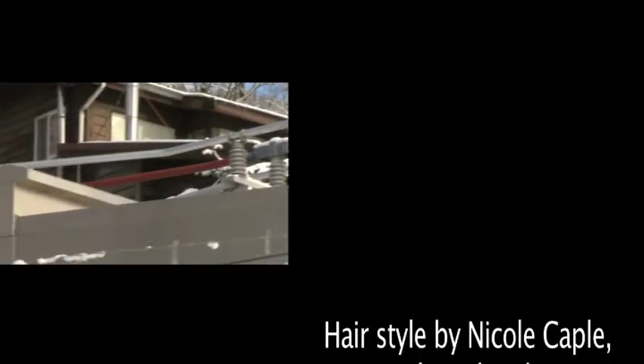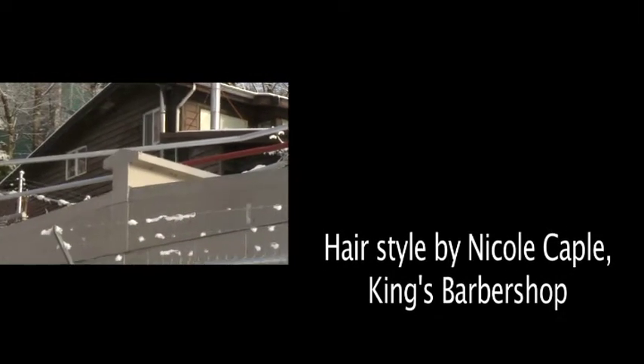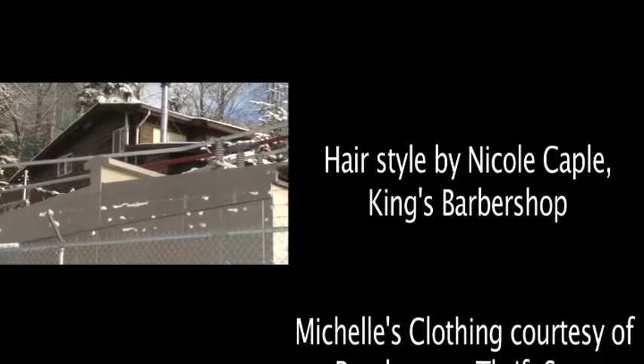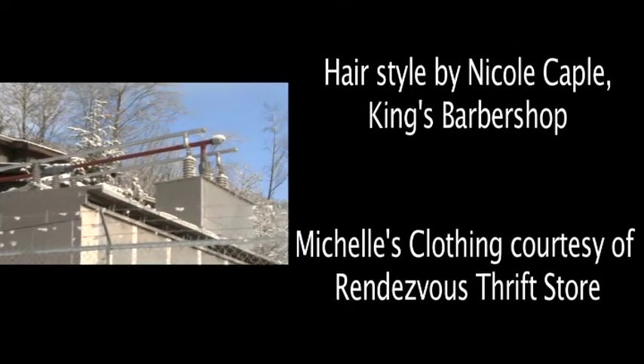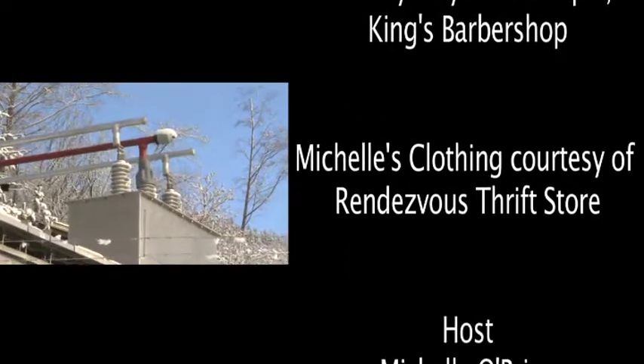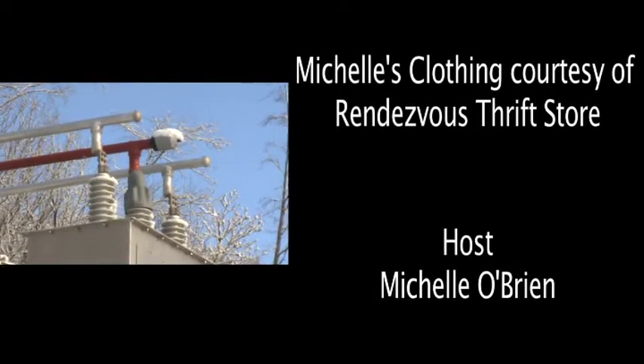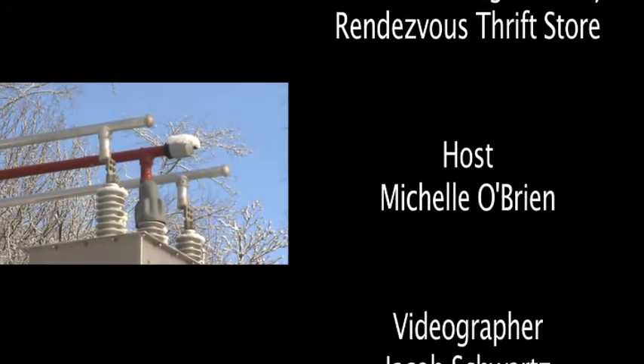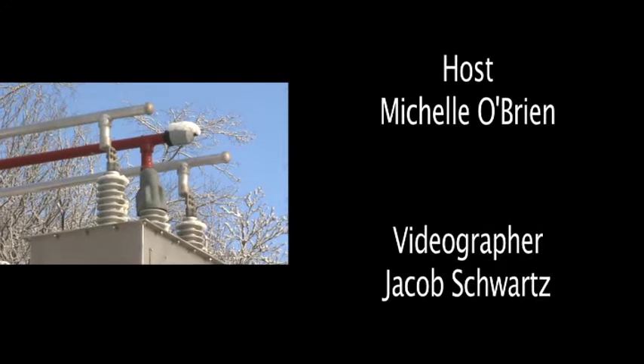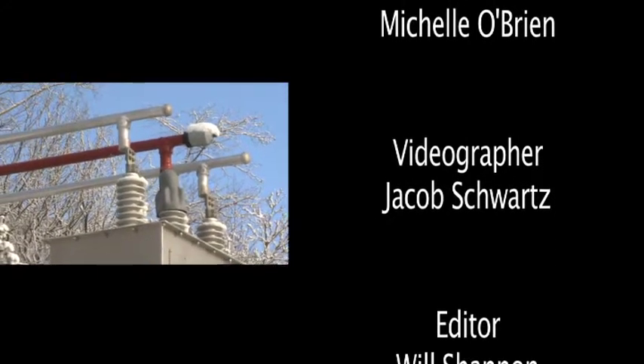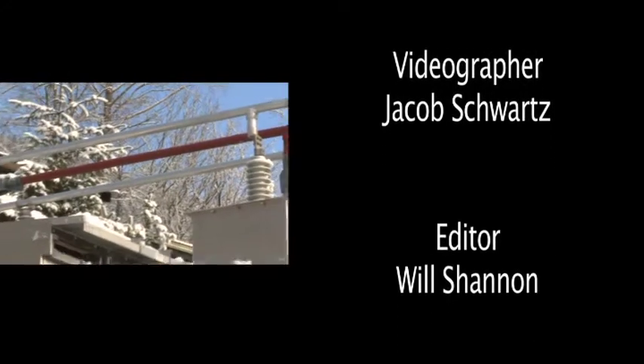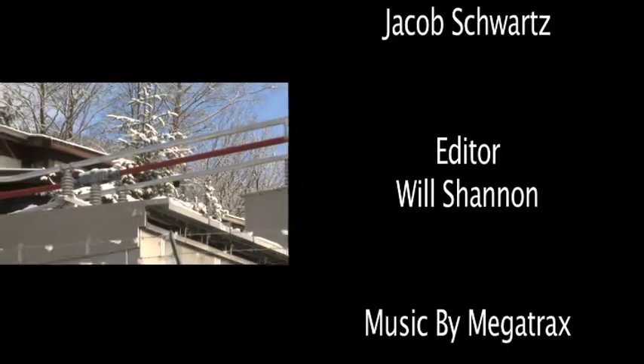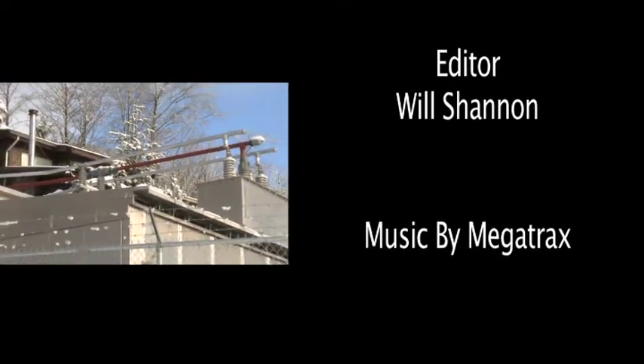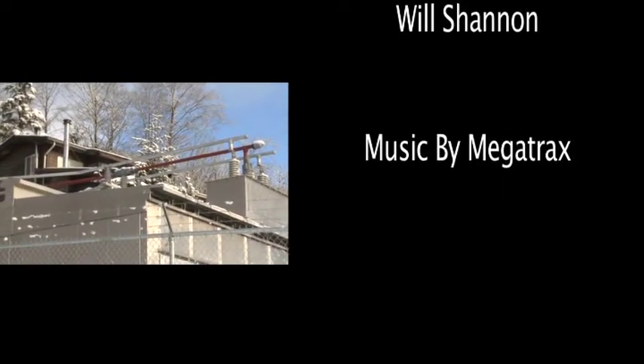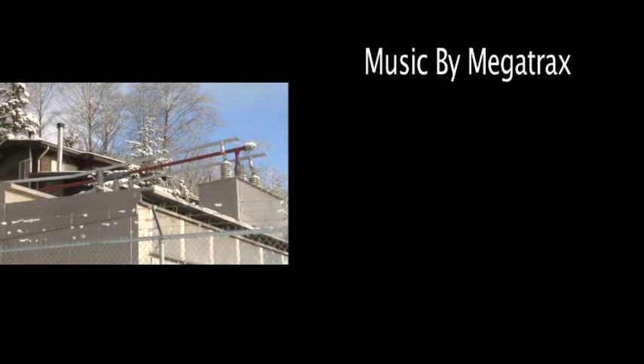There are conductors that are also taped for avian protection, so if a large bird wanted to sit there, its wings wouldn't span across. The easiest way to protect for avian use was to insulate that center phase, so it's set up so a bird can sit on it and nothing will happen, it won't touch the other phase. No more eagle outages.